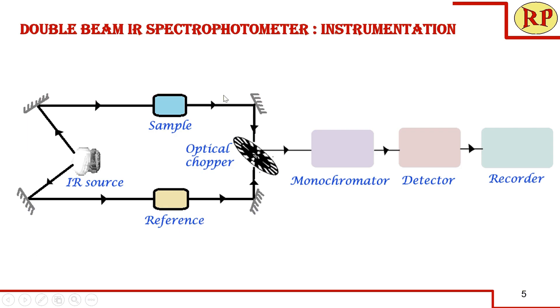Now we will look into the instrumentation part of the double beam IR spectrophotometer — we should not confuse this with FTIR, as this is a different dispersive instrument. An IR source is present here; we can use a Nernst glower, Nichrome coil, or Globar silicon carbide. In all cases, when heated between 200 to 1,200 degrees centigrade, IR radiation is produced. In this double beam design, a double beam is generated and one beam passes through the sample and the other through the reference.